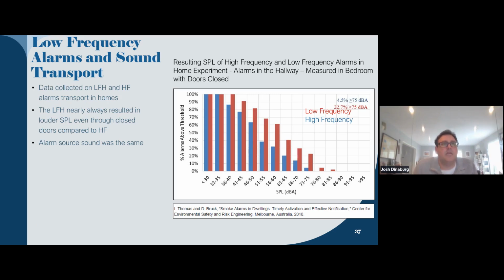So this is actually a study evaluating that, also done by Dr. Bruck. And they put alarms in parts of the home, a full-size home, multiple floors, multiple bedrooms. The one I'm showing here is where the alarm is located in the hallway, and the measurement is made in a bedroom with a door closed in between. So a non-compliant installation, but how alarms may be installed in many homes, if they're lucky to have one in the hallway even, and how alarms used to be installed.